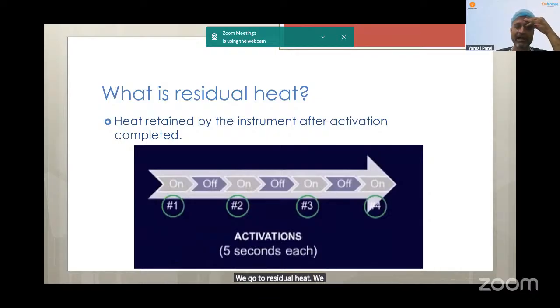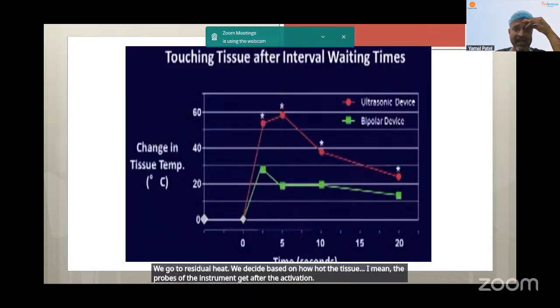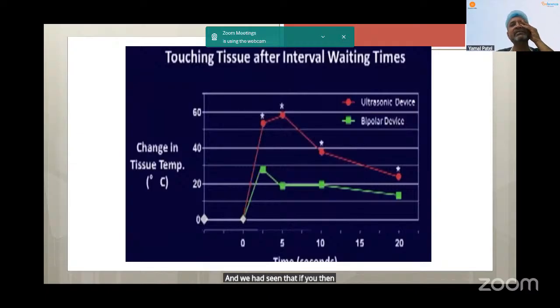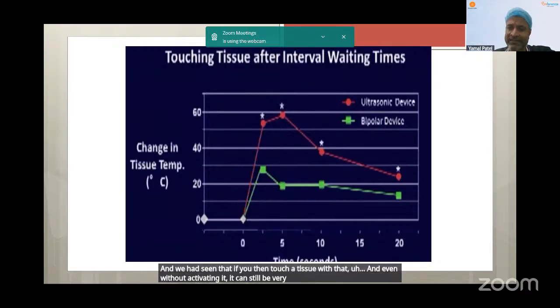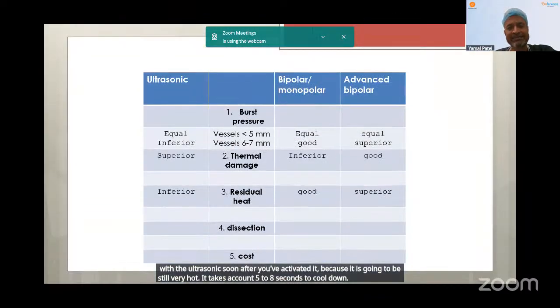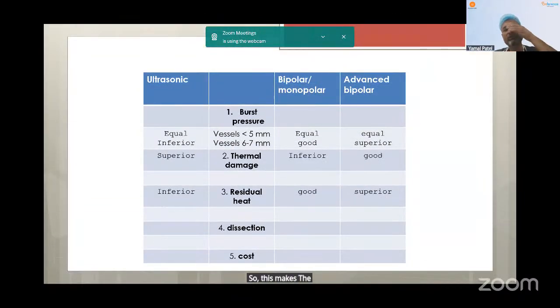We decide based on how hot the tissue probes of the instrument get after activation. We had seen that if you touch tissue with that end, even without activating it, it can still be very hot when it's ultrasonic as opposed to when it's bipolar. Hence, you have to be extra careful not to touch very friable tissue, like the urethra or the bladder or the bowel, with the ultrasonic soon after you have activated it, because it is going to be still very hot. It takes around 5 to 8 seconds to cool down. So this makes the advanced bipolar superior to ultrasonic or the traditional bipolar and monopolar.